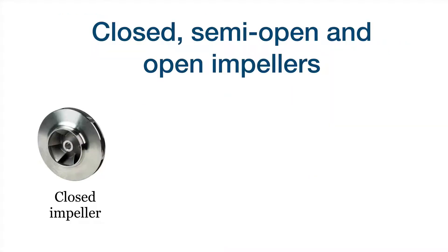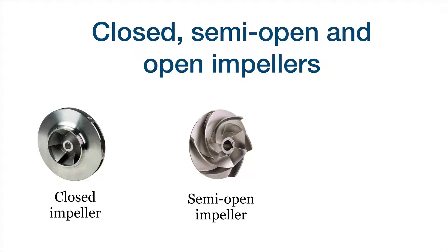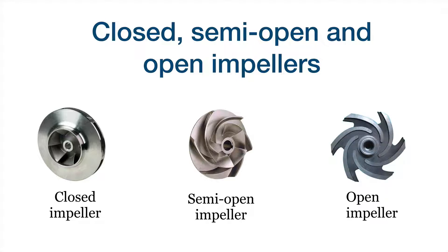Impellers: the most common impeller is the closed impeller, where the blades are covered by two walls. This type of impeller is normally used for clean fluids. This is a semi-open impeller — only one wall, the back wall, is present. This type can be used for clean fluids and also for fluids containing solids. And this is an open impeller — there are practically no walls.